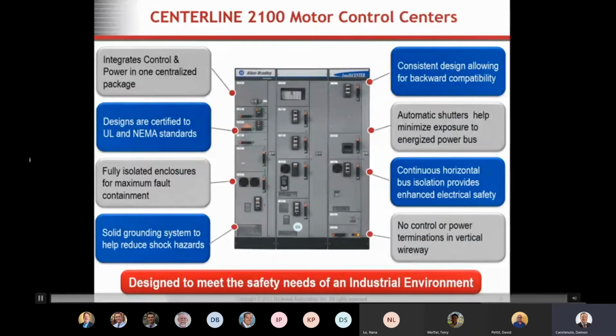This slide here just talks about some of the integral parts of the MCC as a whole, right out of the factory without any of the options that we're going to talk about here. Power is in a centralized location. Basically, it's a combination starter with a disconnect to help with maintenance and keeping things up and running. We mentioned it's a UL and NEMA MCC. We talked about the fault containment, consistent design, backwards compatible. I did do the caveat of that to make sure it's a Series P or later. Automatic shutter, so as the unit's removed, the vertical stabs are automatically closed. Horizontal isolation, obviously, for the KAIC rating you have, and there's no control or power terminals in the wireways, which also helps with the isolation.